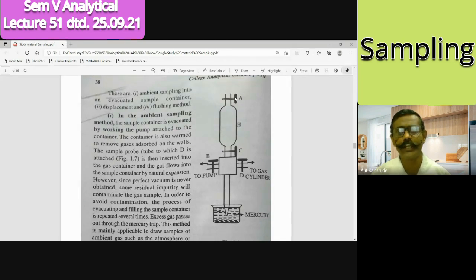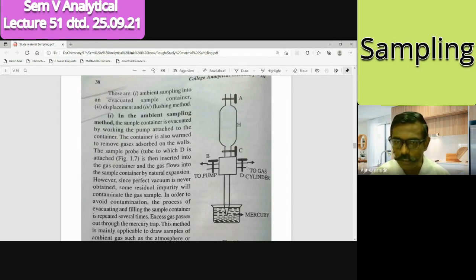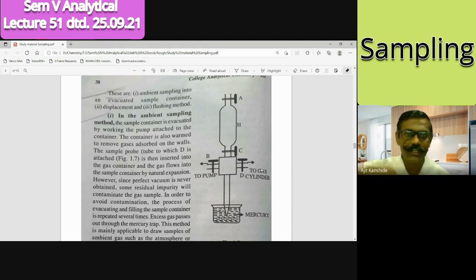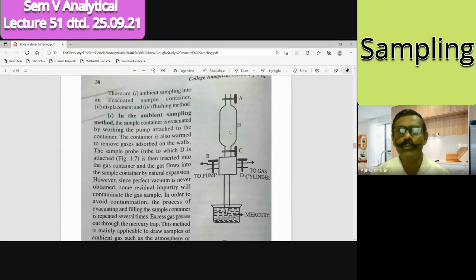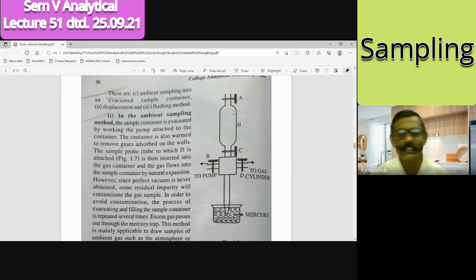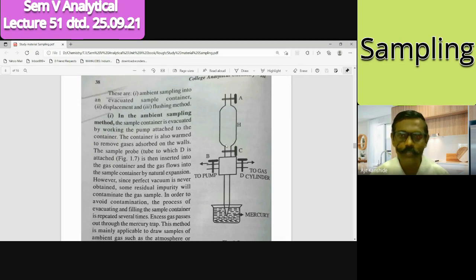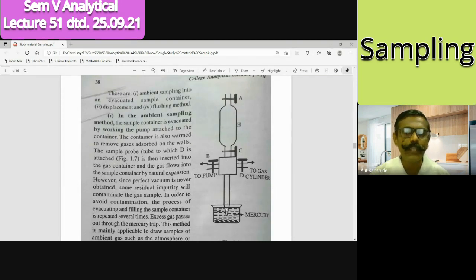Afterwards, close knob B and open knob D. Knob C should also be open. If the gas quantity is small, knob A should be closed; if more quantity is available, do flushing first then open it. From the cylinder, through pressure the gas will enter the sample tube H, because the gas in the cylinder has pressure. If pressure is insufficient, we can apply the suction pump at end A to draw gas in.